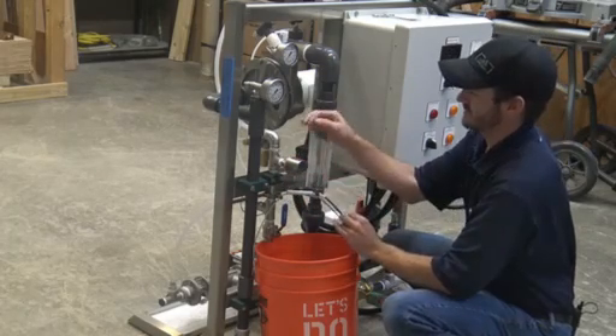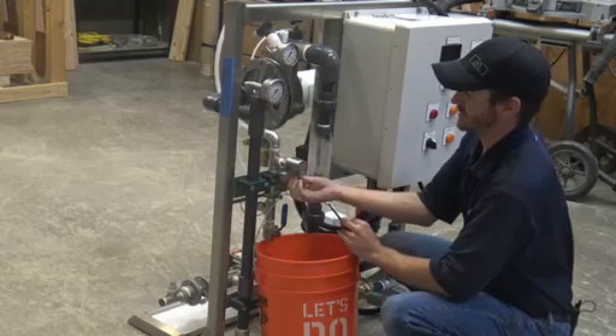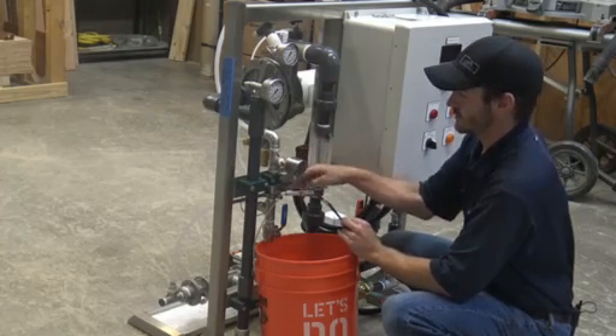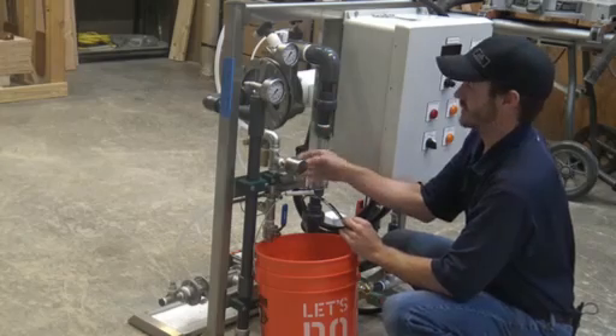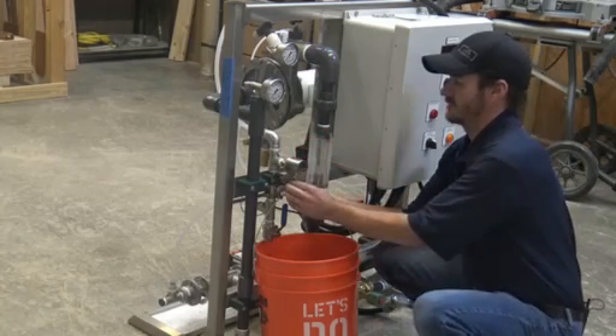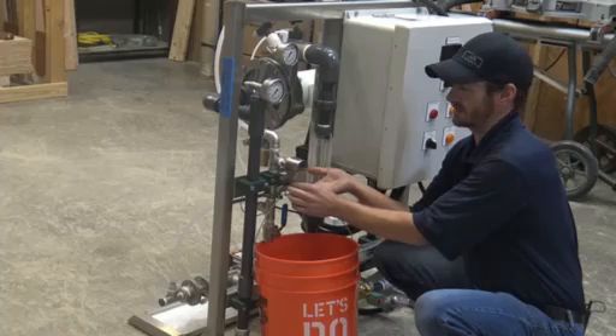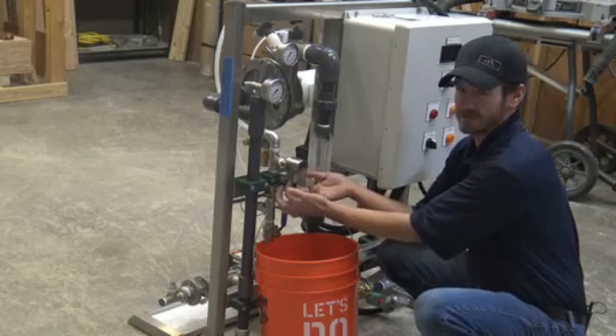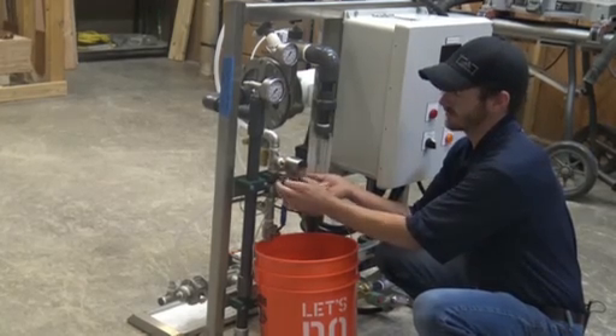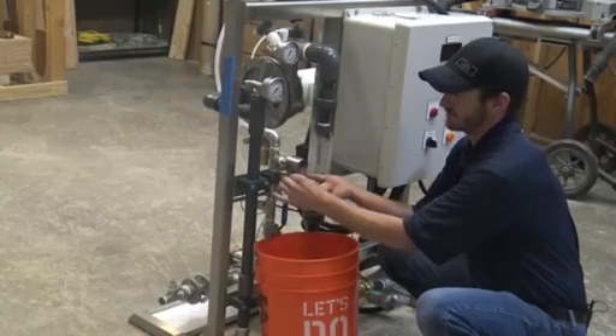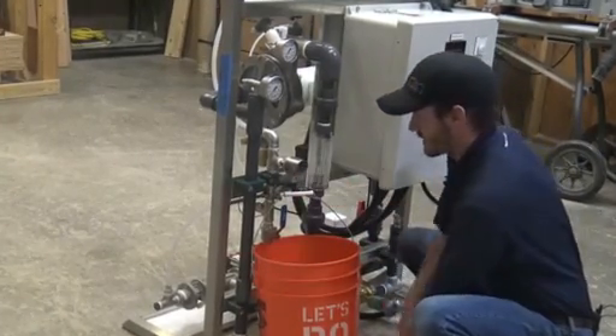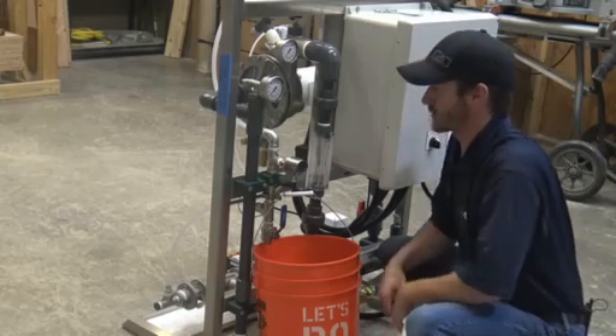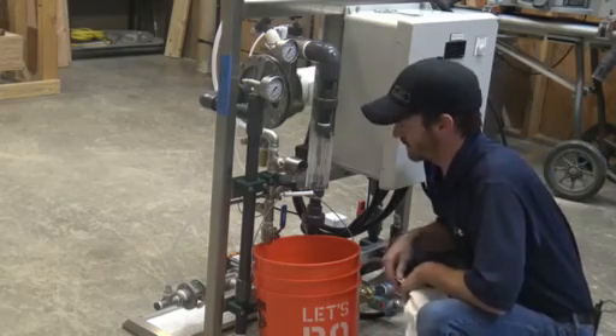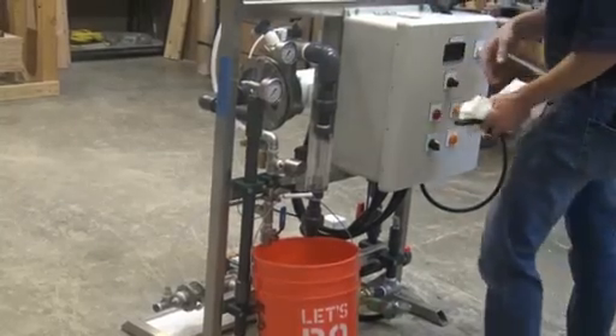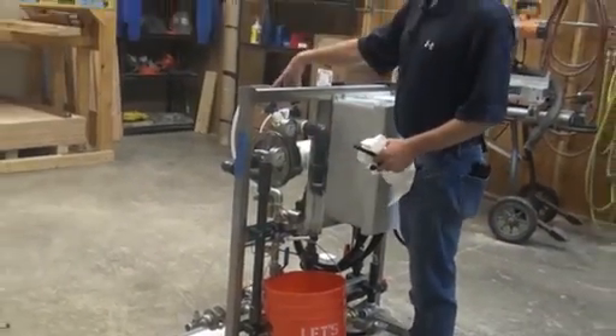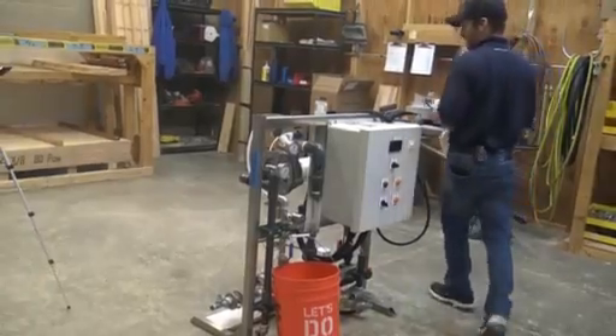When putting the thermal flow sensor back in, make sure your electrical connection is pointing to the inlet of the polymer assembly. Be careful when pushing this back, so you don't fold over any pins or damage any pins inside of the thermal flow sensor, and then tighten your screw up. That's about all it is for the thermal flow sensor. Since you have all the pressure released everywhere, we can move on to the VeloCheck valve.